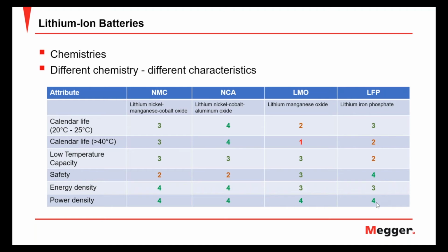Another common battery that's used, and a lot by Tesla, is the LFP, lithium iron phosphate. This is probably one of the more common ones we see in other applications. They don't quite have the same amount of energy density and are not as good at low temperatures, but they have a much higher safety rating, okay? So when I say safety rating, keep in mind what we're discussing here is actually the ignition point of the electrolyte. These electrolytes are flammable, and they ignite at different temperatures. So what this means is that in a lithium iron phosphate battery, the electrolyte has to get hotter than it would in a nickel manganese cobalt in order to ignite.